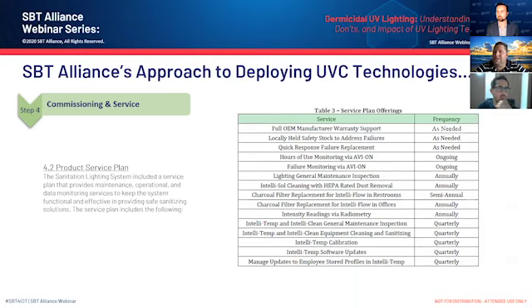Quick response to failure replacement, hours-of-use monitoring, failure monitoring, and lighting general maintenance inspection. We work with IntelliSol cleaning, since that fixture is essentially an HVAC unit more than a light—it needs to be cleaned, the HEPA-rated dust removed, the filter removed, and the charcoal filter replaced.